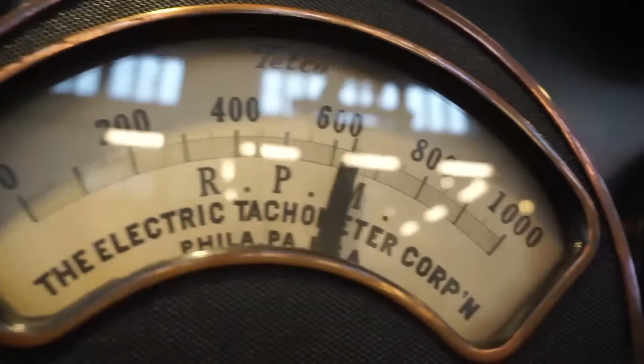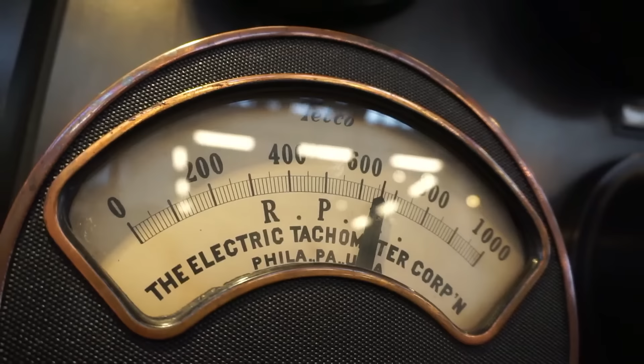You can hear the motor that is revving up, and here we can follow the speed of the motor, and it's just now about 610, 620 RPM. We are also following the voltage to the motor. Just now it's 2300 volt. Our target voltage is about 1900 volt. When the speed of the motor reaches 700, Anders now will close the next knife switch to magnetize the alternator.